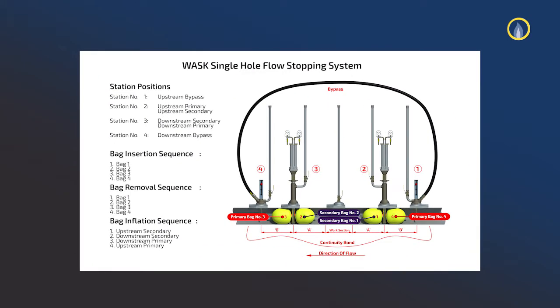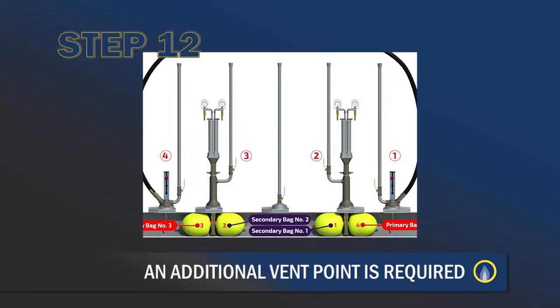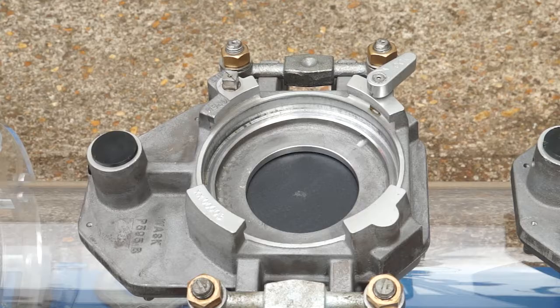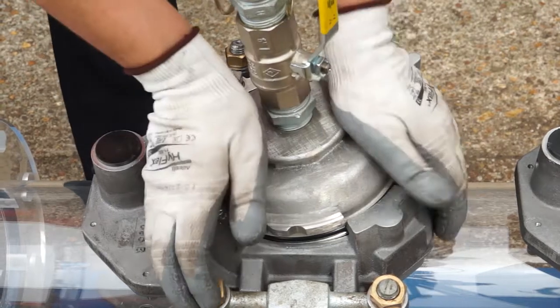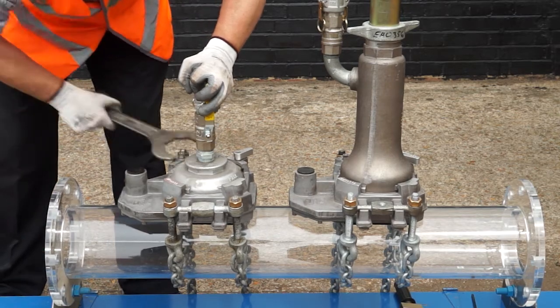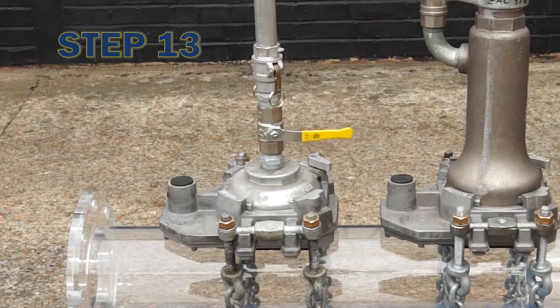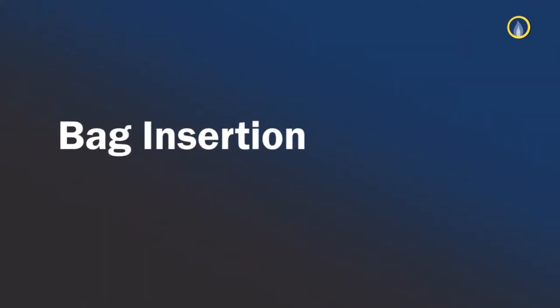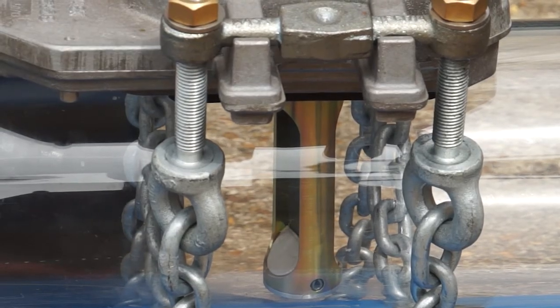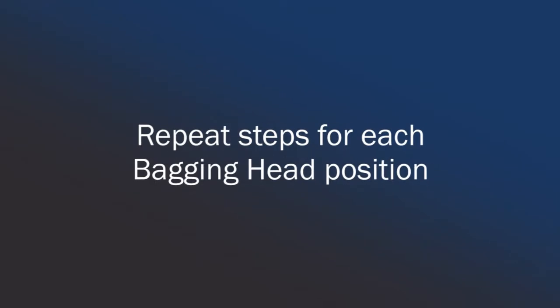The bypass is now commissioned. An additional vent point is required when using the WASK system, which should be located within the section of main to be cut. An additional base, undercarriages, and securing chains are supplied. Locate the vent head into the base and rotate clockwise to engage bayonets. On Mark II bases, turn the vent lock handle to secure in position. Attach a vent stack to the head. Ensure that the 1-inch vent valve on the canopy is in the closed position. Loosen the canopy wing nut clamp and insert the bag tube assembly into the main to a stop. Rotate the bag tube assembly to align the upper bag tubes with the axis of the main. Re-clamp. Repeat steps for each bagging head position.